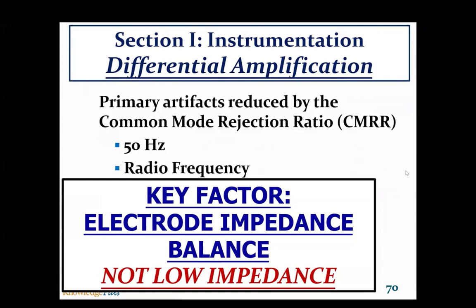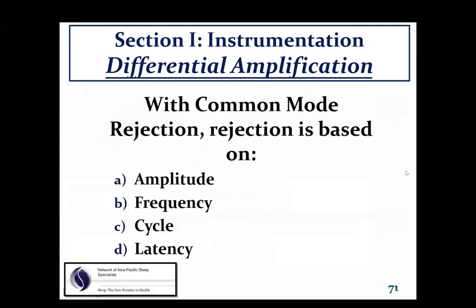Not all noise is electrical. Our lab was right next to the page operators, and whenever they paged, we got a little ziggy ziggy ziggy on our recording, and we ended up having to copper shield the room, which was very expensive. But turning on the 50 hertz filter did not help. So the key factor in eliminating noise and taking advantage of the common mode rejection ratio is to have balanced electrodes. Not, yes, low impedance, but they have to be balanced.